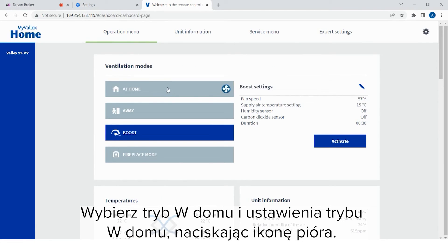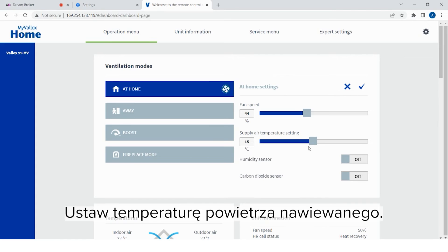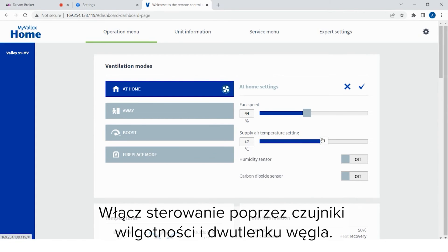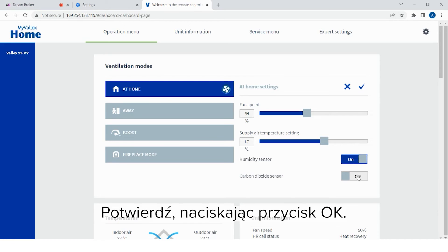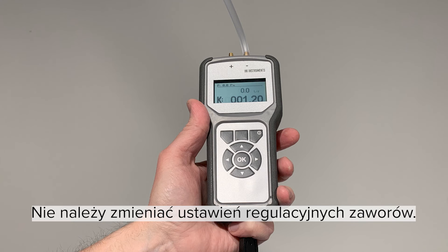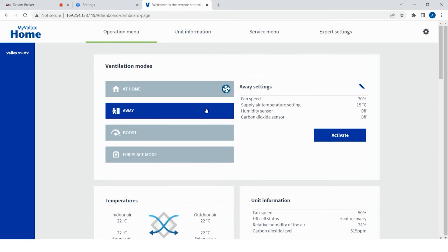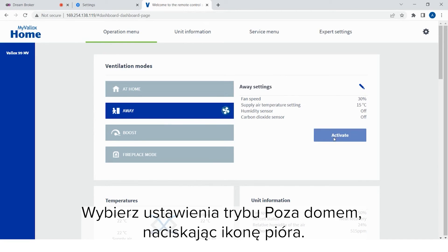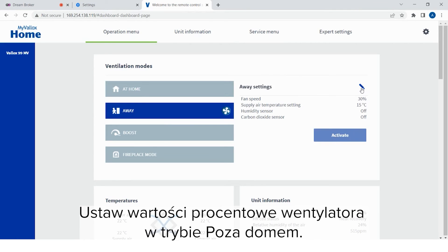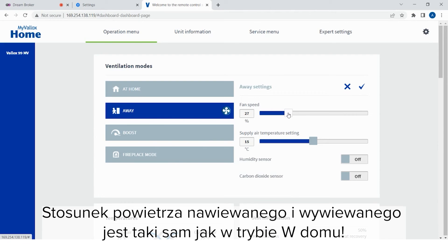Select the at-home mode and the at-home settings by pressing the pen icon. Set the supply air temperature. Turn on humidity and carbon dioxide base controls. Confirm by pressing OK. Adjust the supply and the extract air flows of the away mode. Measure the air flows from the supply and extract air valves. Do not change the adjustment settings of the air valves. Select the away mode and turn it on. Select the away settings by pressing the pen icon. Set the fan percentage of the away mode. The supply and extract air ratio is the same as in the at-home mode.